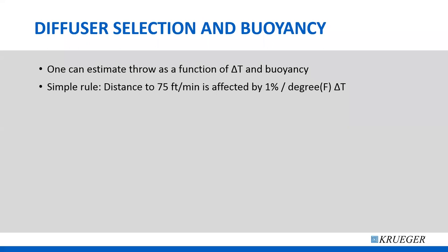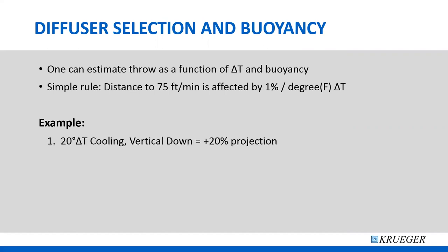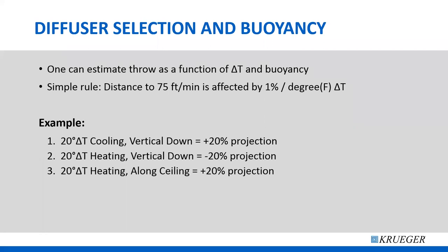The rule is 75 feet-per-minute, 1% per degree delta T. Let's say a jet has a 10-foot throw down and I have 20 degrees of cooling — it's going to go 20% further, or two feet further. That same jet with 20 degrees of heating is going to go 20% shorter, or only eight feet. Going from 20 degrees cooling to 20 degrees heating results in a 40% change in throw. That's a big deal because you have to size the diffuser and airflow so the heating airflow makes it to within four feet of the floor — but then the cooling airflow will enter the occupied zone because it goes 40% further. Along a ceiling, hot air goes further by the same rule: 1% per degree delta T at 75 feet-per-minute.